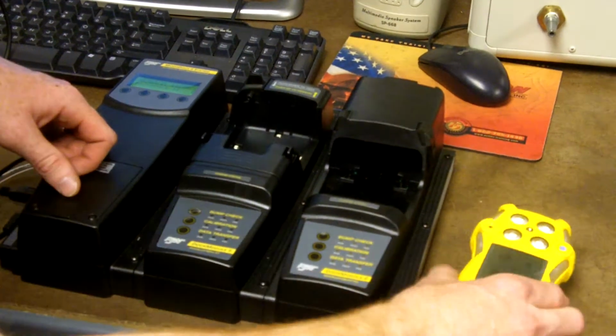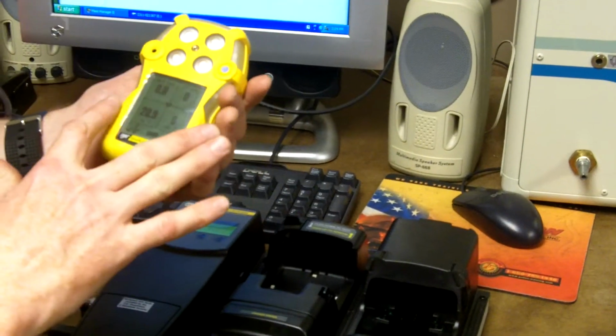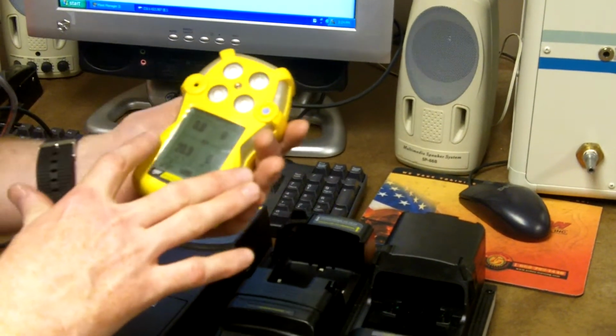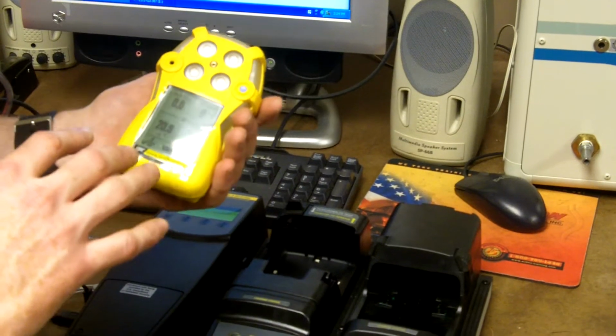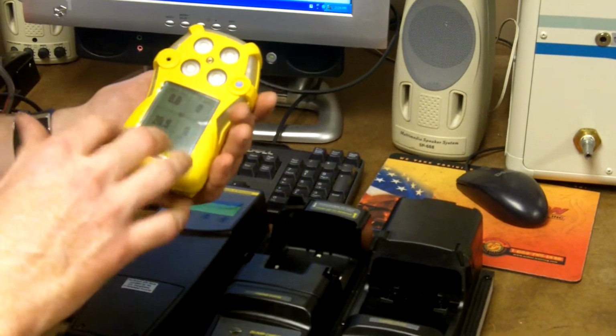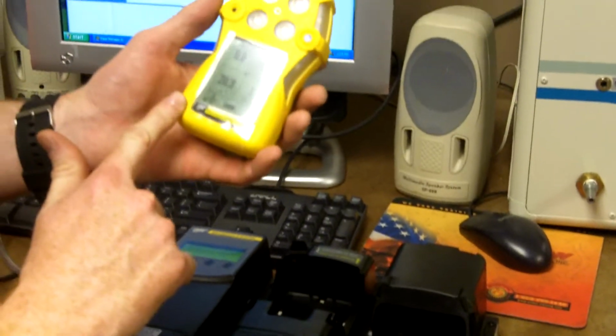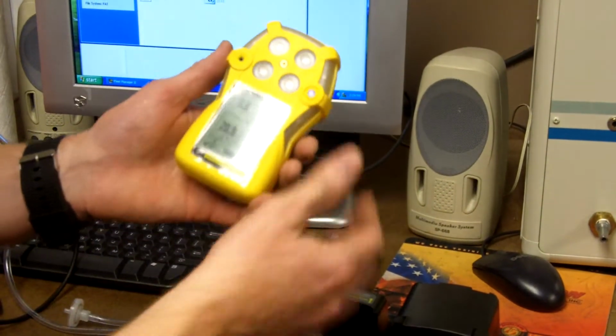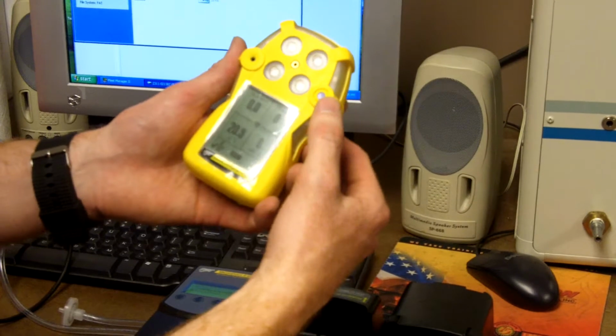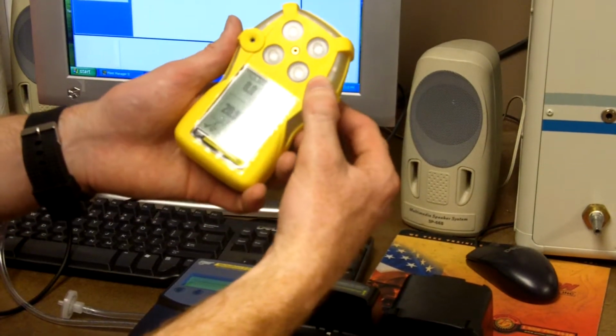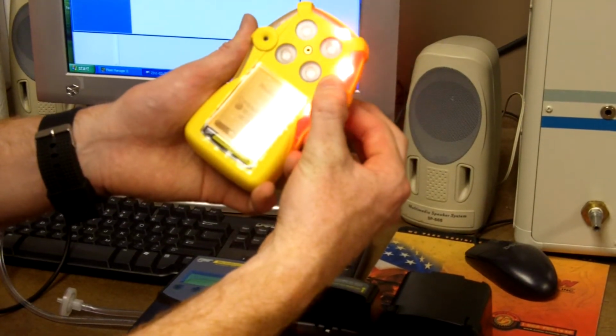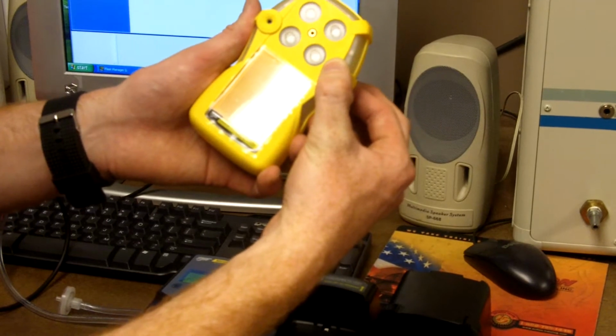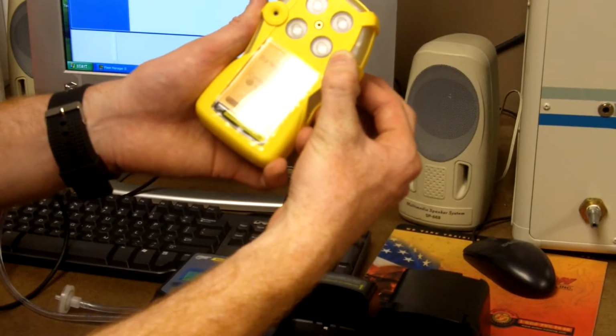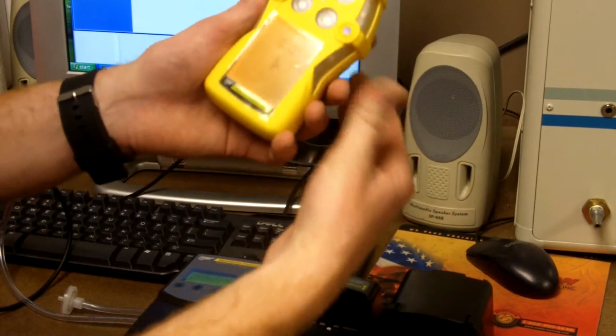So the next thing we need to do is get our gas detector ready to go for calibration. This is calibration. If I wanted to bump check, I'd be able to load this on right now, but I need to first put our gas detector in calibration mode. The way I do that, it's already run through its checks and zeroed out. I'm going to hold the off button. I'm going to continue holding it and not letting go. So it powers off, and then I still am holding it. It starts calibration in 3, 2, 1, and it says you need to put the gas on it.